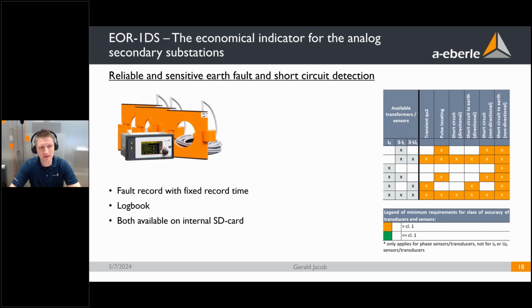The device has fault records on board. Here is set with fixed record time, so you can parameterize it and then it's fixed. So you can only record 200 milliseconds, but you can also record 4 seconds, for example. And in addition, the device also has a logbook, and both the fault records and the logbook are saved on an internal SD card. So if you want to have access to this logbook and fault records, you have to remove the internal SD card and read it out in your laptop.